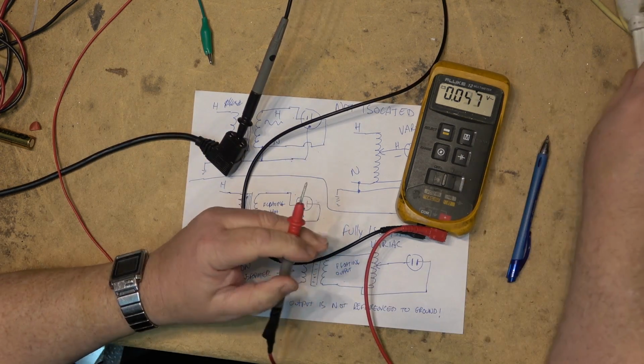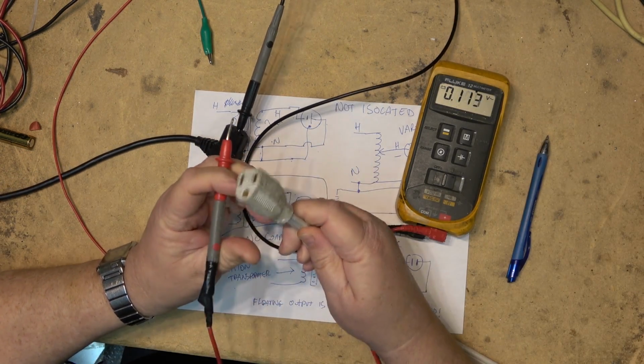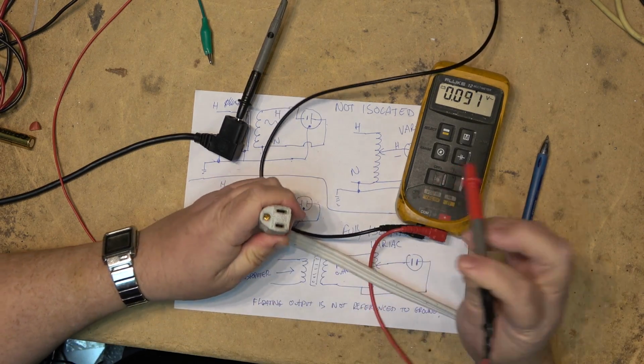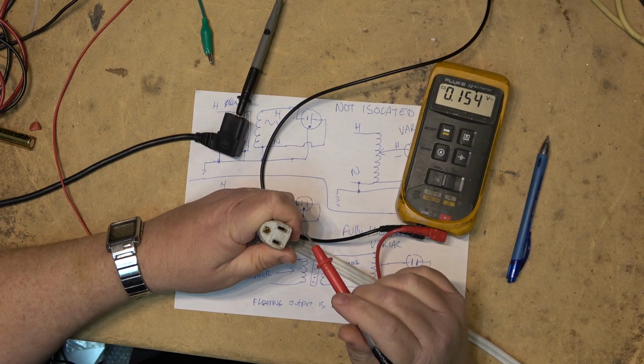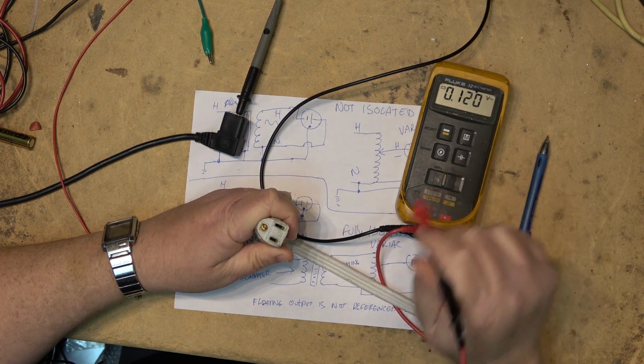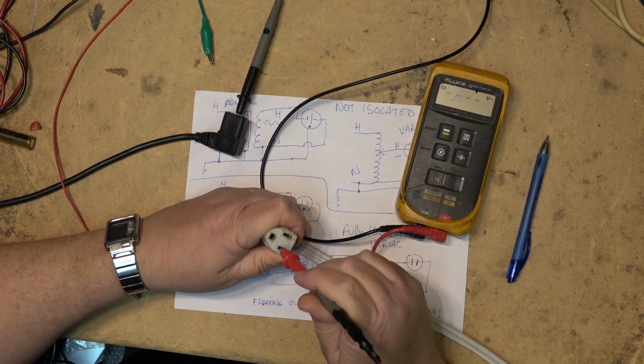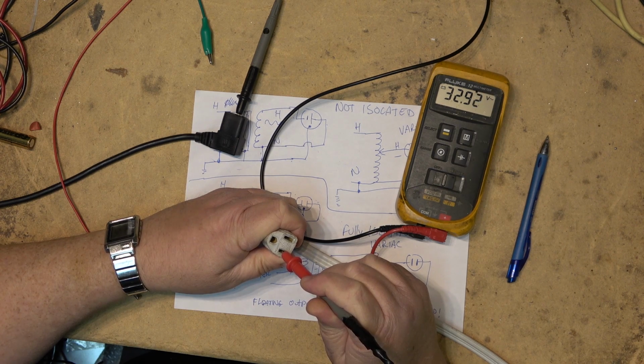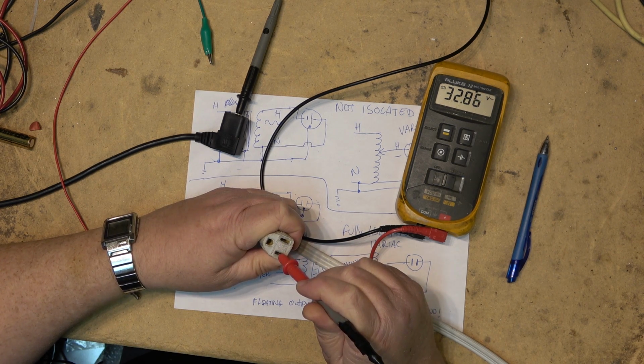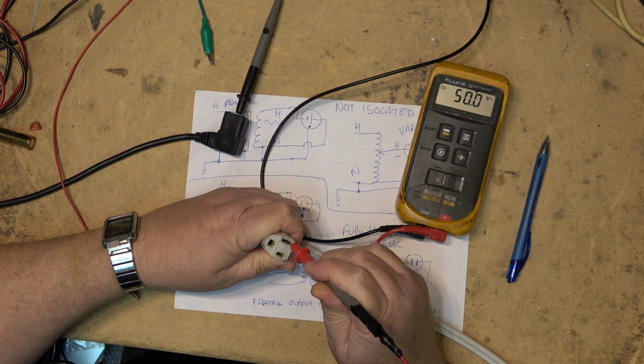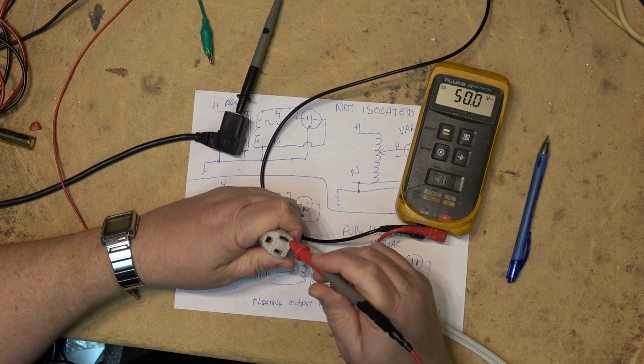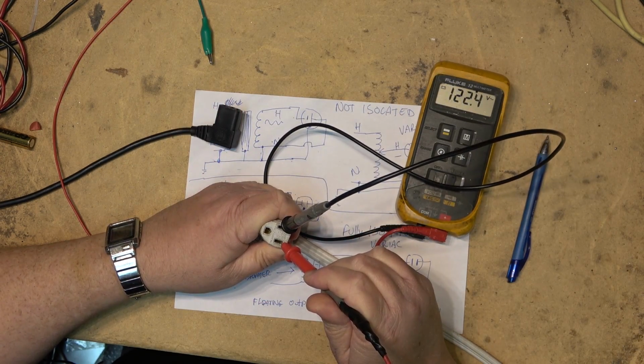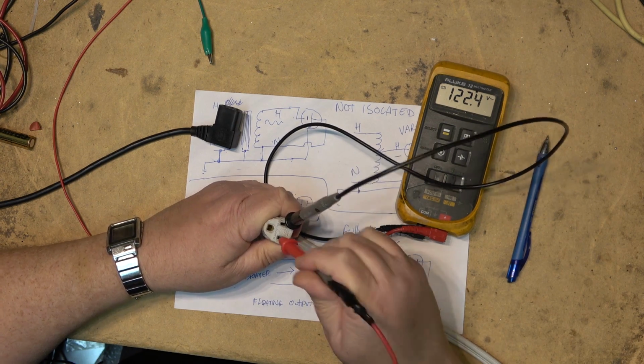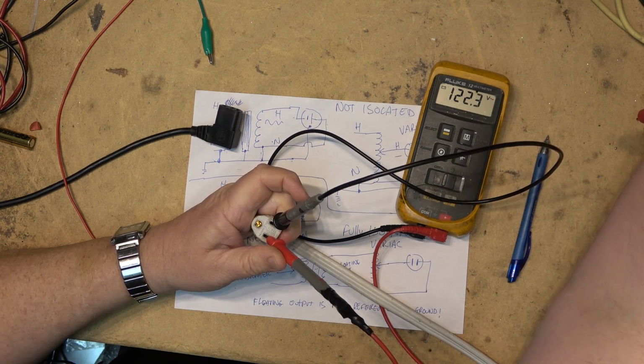Now, if I go over to my isolated cord, we will see that there is not 120 volts on them. In fact, because they're floating, there is going to be some induction picked up, just because this is a high impedance meter. So when I measure, I'm seeing about 32 volts on one side. Okay, I guess that's the neutral side. And the other side, I'm seeing about 50 volts. If I measure between these two, I've got the full, whatever my Variac is set for, 122 volts. And I can adjust that up and down with my Variac.